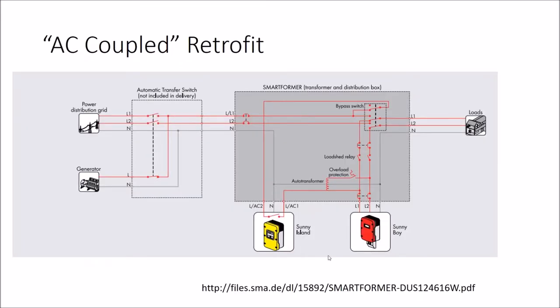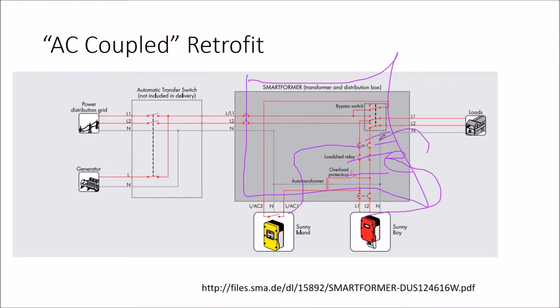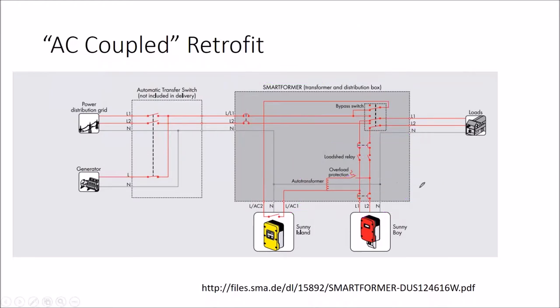There's a few ways to install a battery bank. The easiest way is what's called AC coupling. AC coupling is when you have your electric service panel and you've tied your solar inverter in at the bottom of the bus bar, and then your battery inverter gets installed right next to it, again at the bottom end of the bus bar, until you get up to 20% ampacity per the 120% rule we talk about in the solar programs.